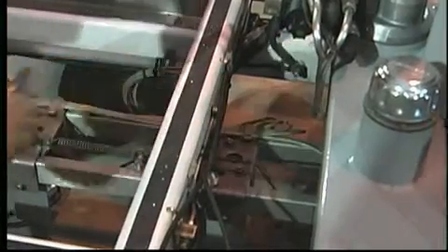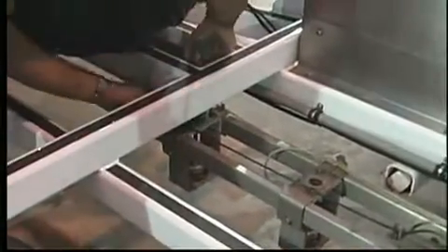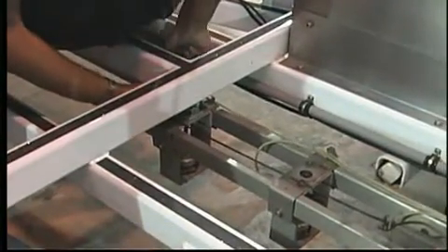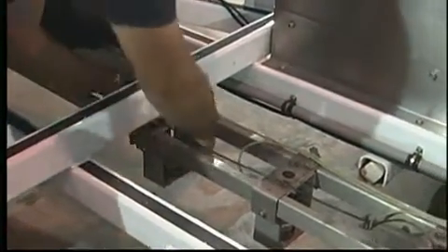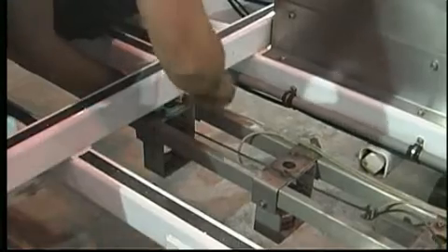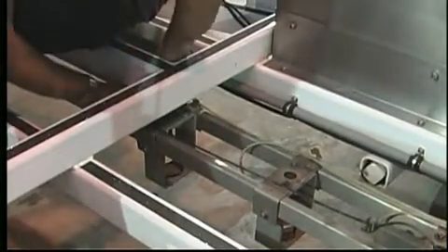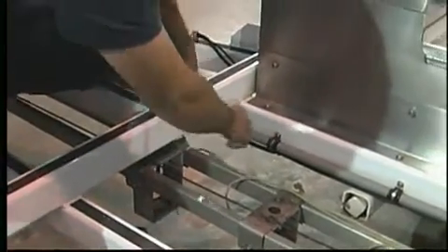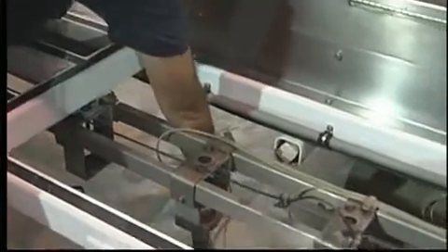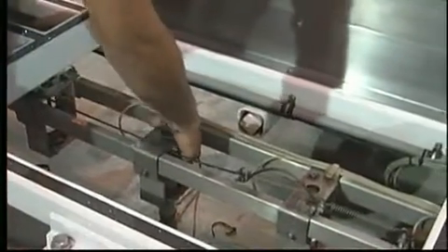One of the first steps after getting to the calibration center is removal of the deflection sensors from their holders. They have to be removed from the FWD and placed in stands used in the calibration of the deflection sensors. The sensors are usually removed by the FWD operators because they know their own machine and are usually more efficient at it than the calibration center operator.